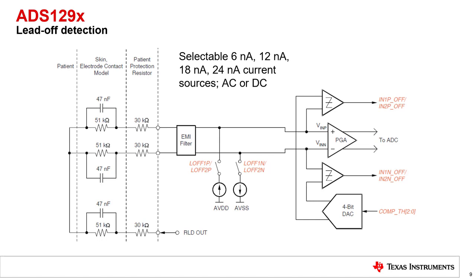In AC leadoff, the same current sources inject an out-of-band square wave current onto the patient. In that scenario, the measured voltage corresponding to the leadoff current source frequency is analyzed to determine the connection between the patient and electrode.